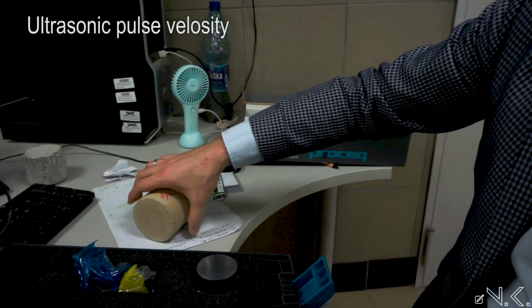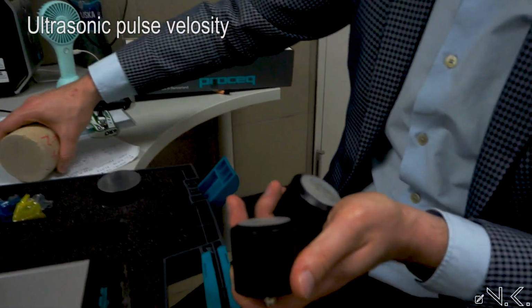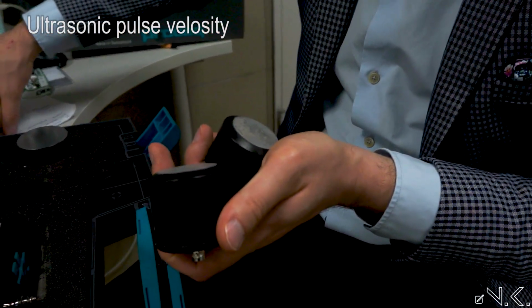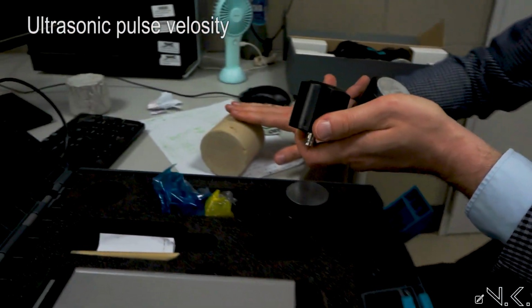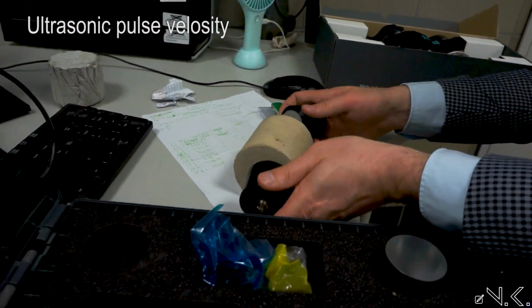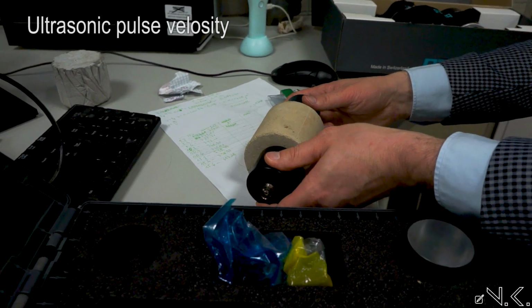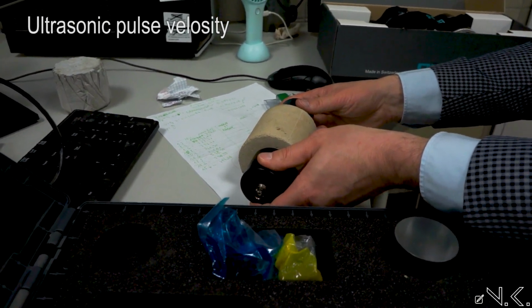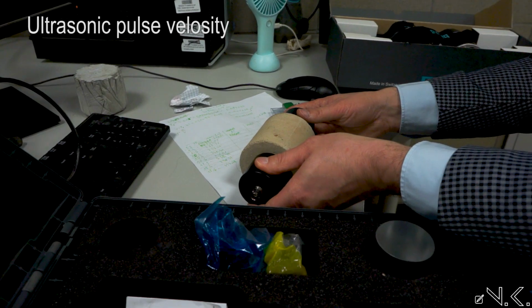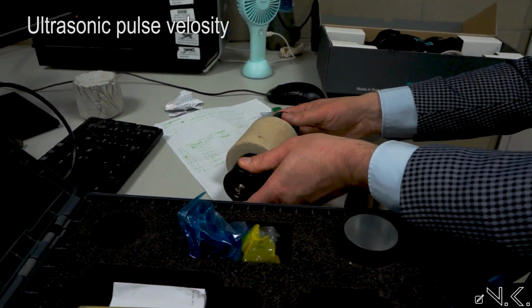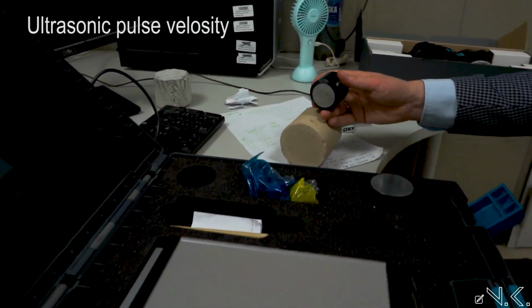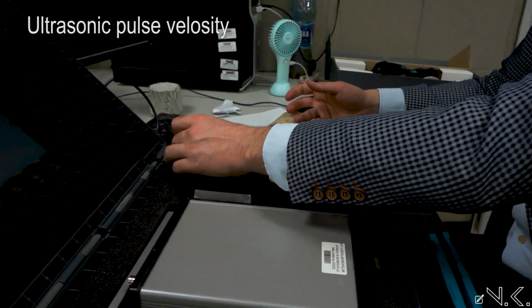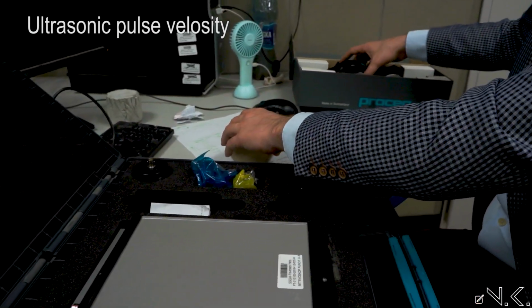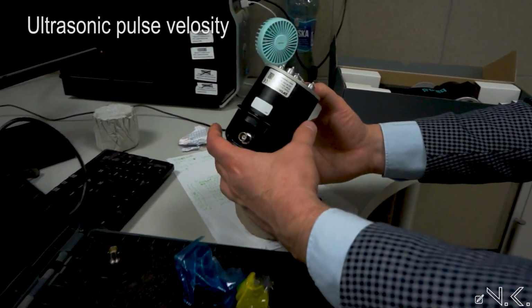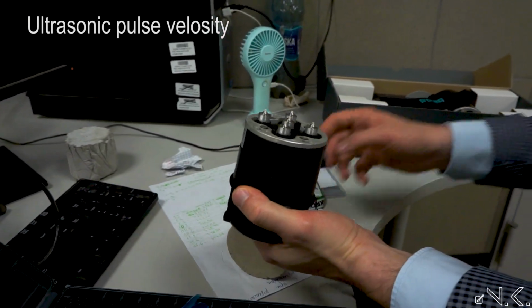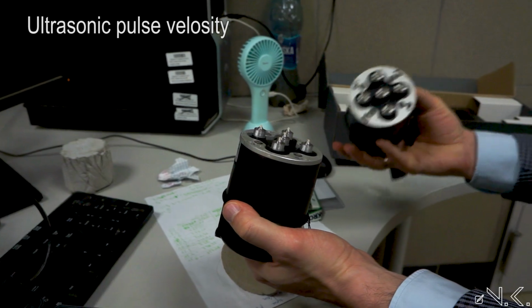So when the sample is ready to be tested, we place it in this horizontal direction, and then we put these two sensors like this. Then the dedicated software takes the measurement, and we can find the velocity of the pressure wave. So this is the pressure wave, and the second option is to measure the shear wave. The shear wave is measured with these two sensors. So this is the first one, this is the second one, and we are doing exactly the same.